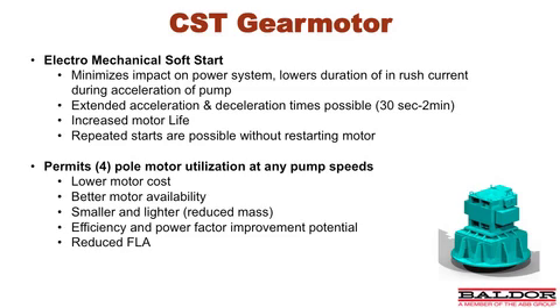The electromechanical soft start minimizes the impact on the power system, thus lowering the duration of inrush current during the acceleration of the pump, and this is significant. We also provide extended acceleration and deceleration times utilizing the soft start methodology. This also provides increased motor life and allows for repeated starts without restarting the motor, as the motor is disconnected from the load through the hydroviscous clutch.